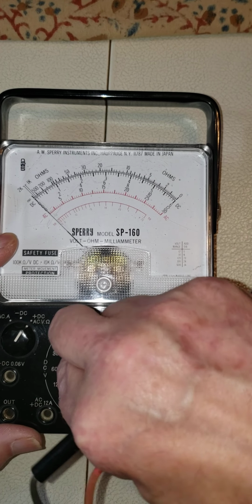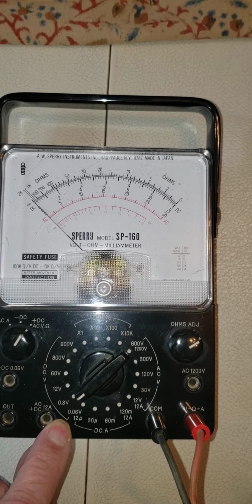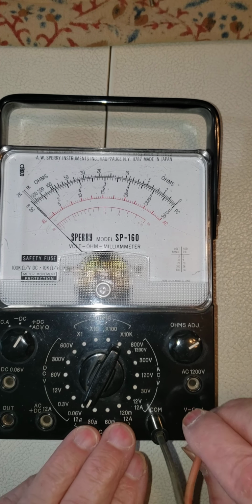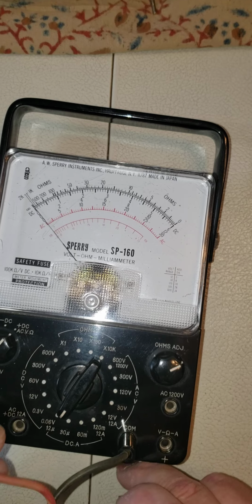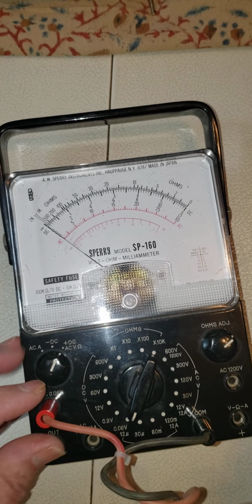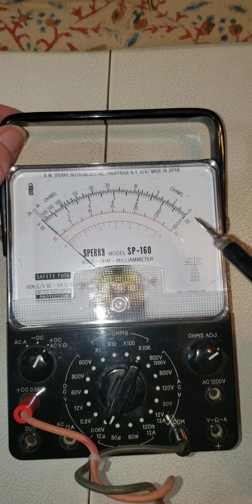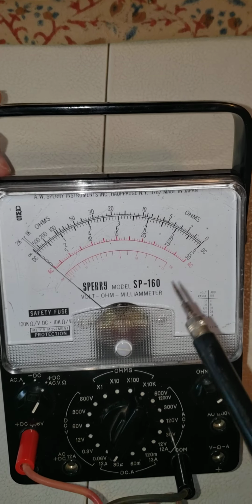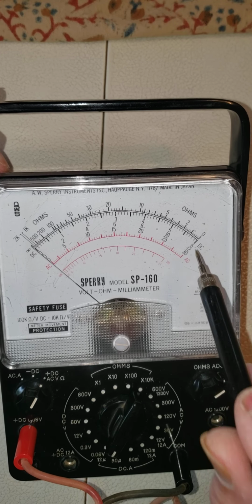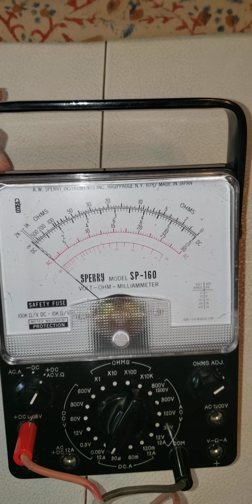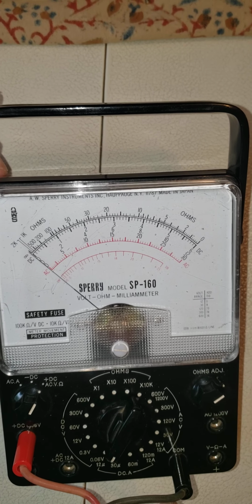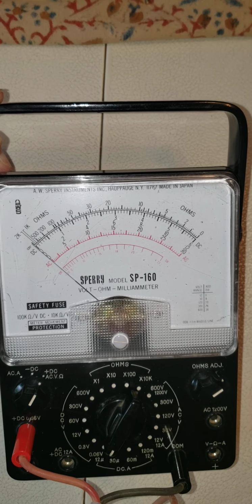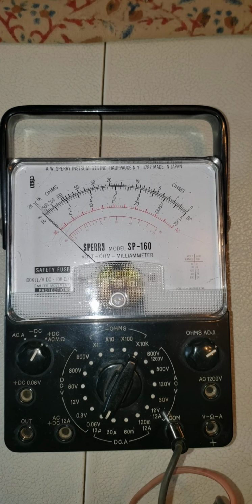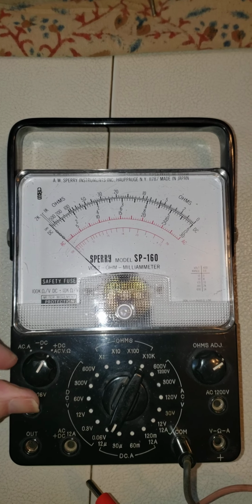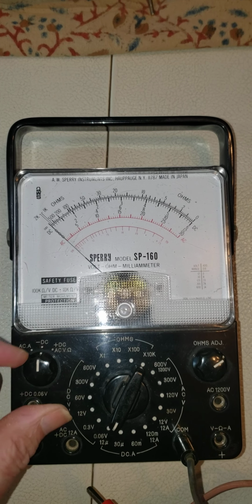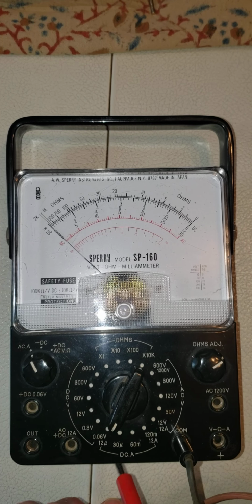Same thing on the DC volts. This actually has a 0.3 volt and a 0.06 volt scale. So you still got a common, and you go to the, that would be the 0.06 volt scale. I don't have anything that small, but if you were to use that, you'd be using the scale that ends in a 6 and putting in the dot and the 0 to make it .06 volts, millivolts. Never really used it for current measurements, but it does have AC amperage. Okay.